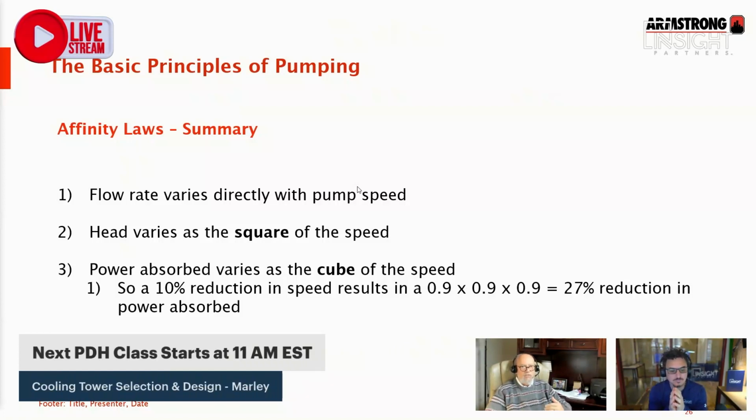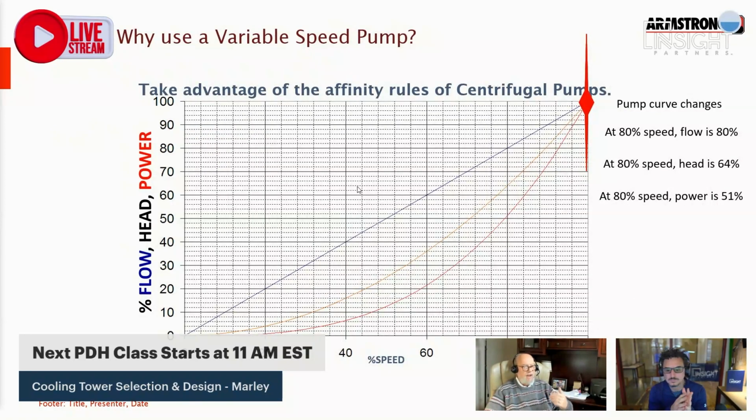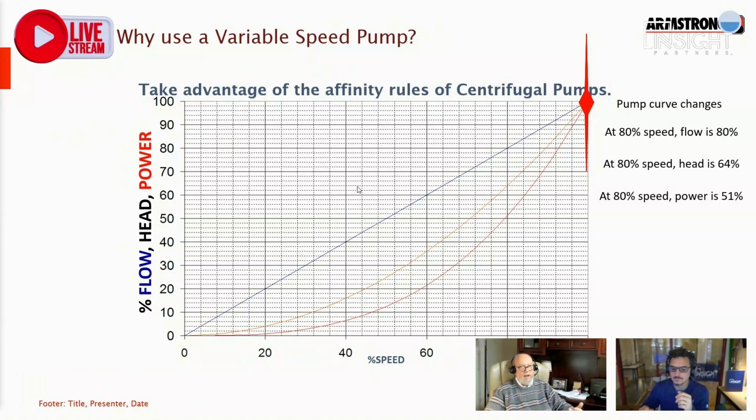So what you want to always do is take advantage of the affinity rules and understand, by the way, that the affinity laws are the same whether we're dealing with pumps or we're dealing with fans. Doesn't change any. So understand this is what's happening.